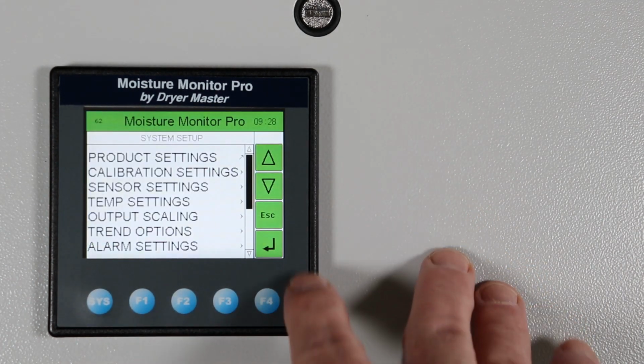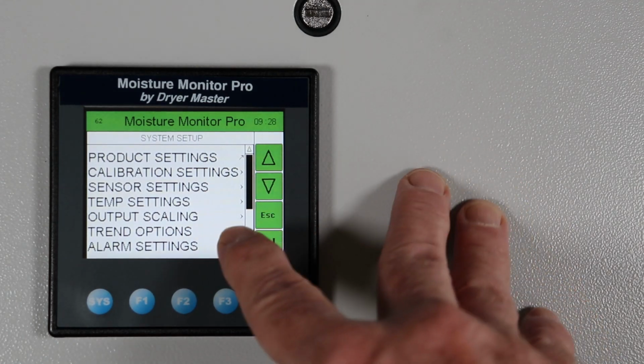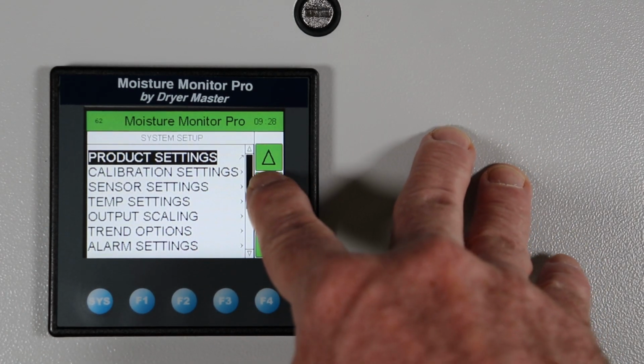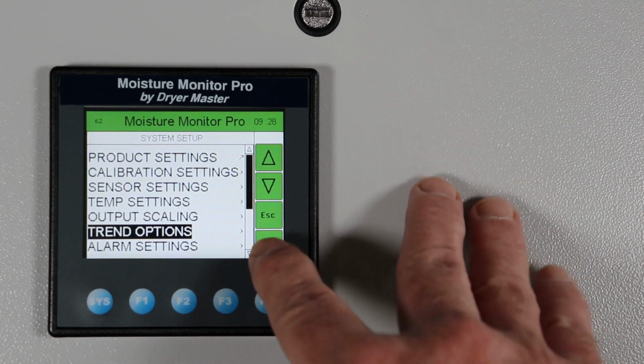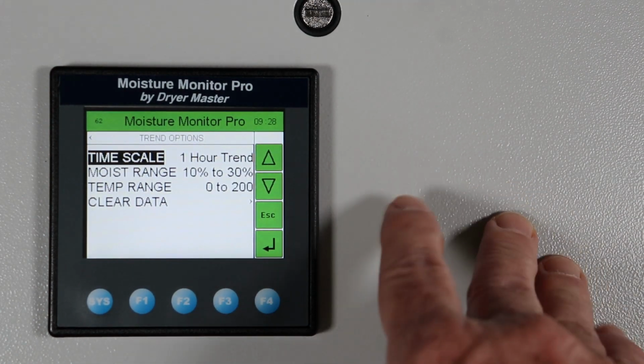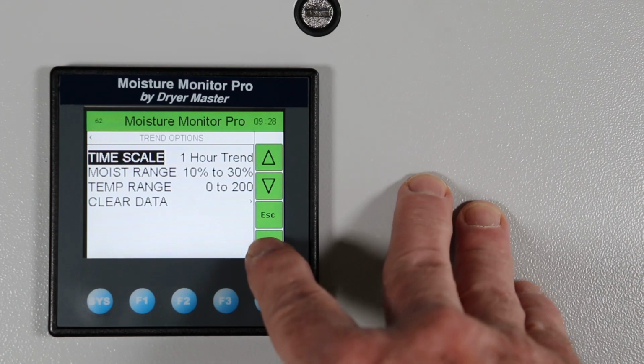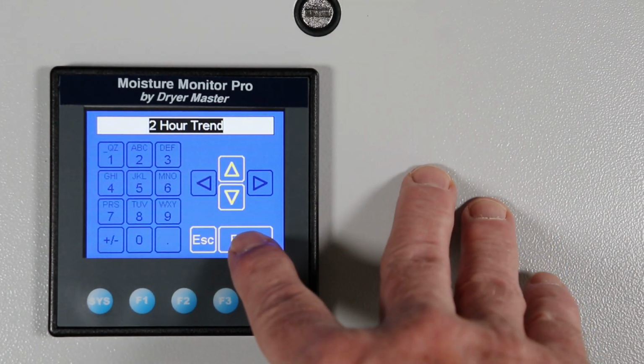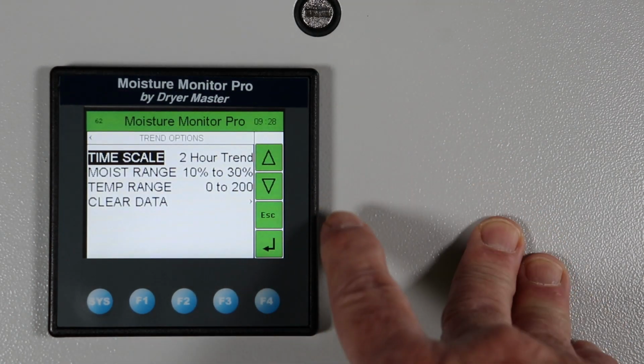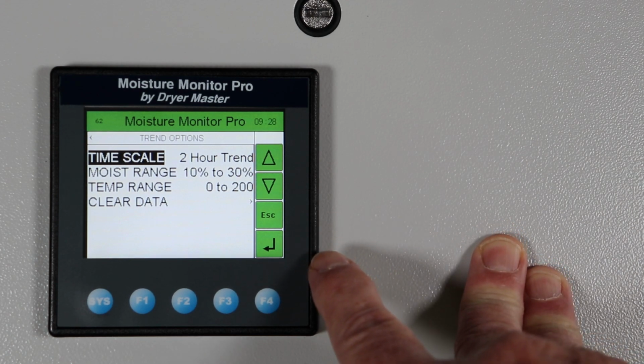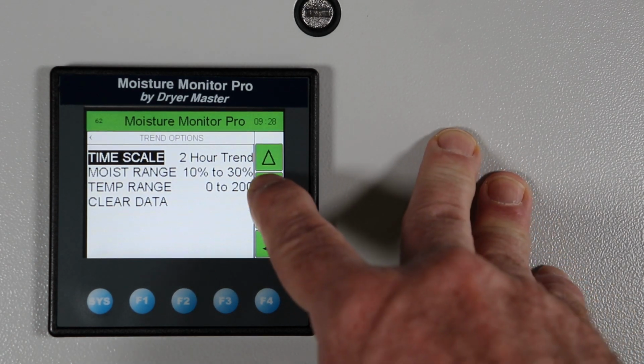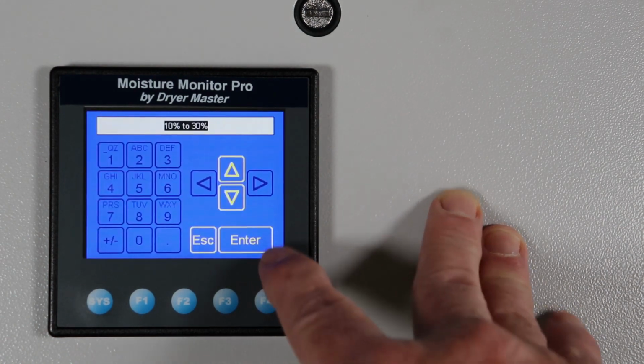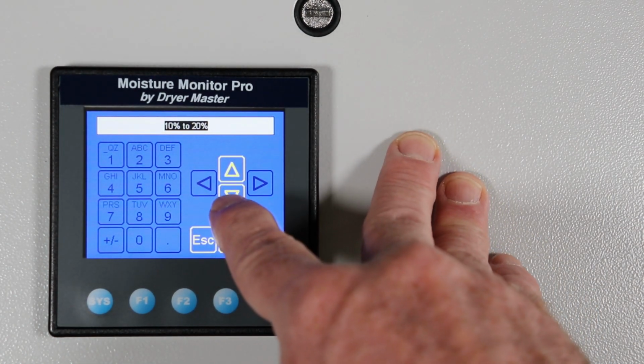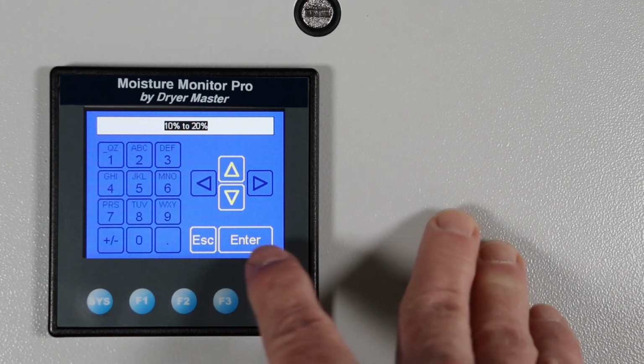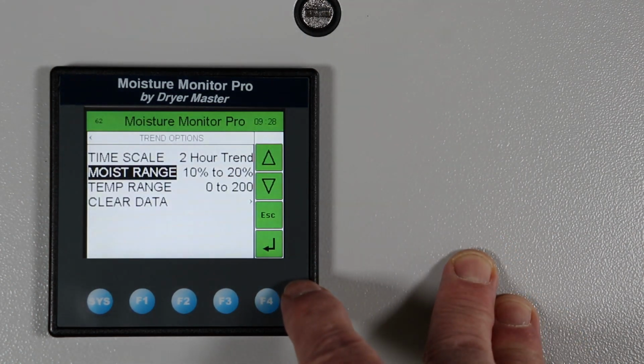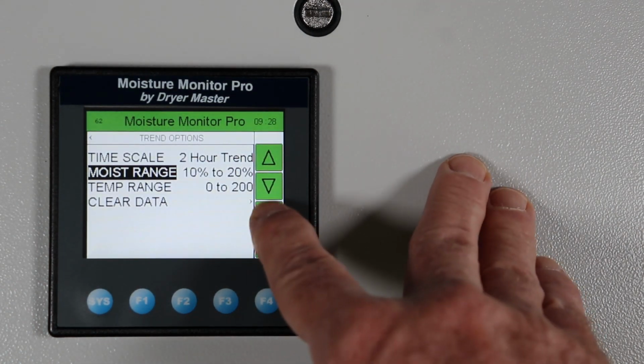6853, Enter, and of course we'll go down to where it says Trend Options, Enter, and we can either have a 1 hour trend, or we can go 2 hour trend. And then you've got different ranges you can set for the axes on your graph. So for example, moisture range, let's change that to 10 to 20% as my range. So we just hit enter, and that'll change the scale. And you can do the same thing for temperature as well.